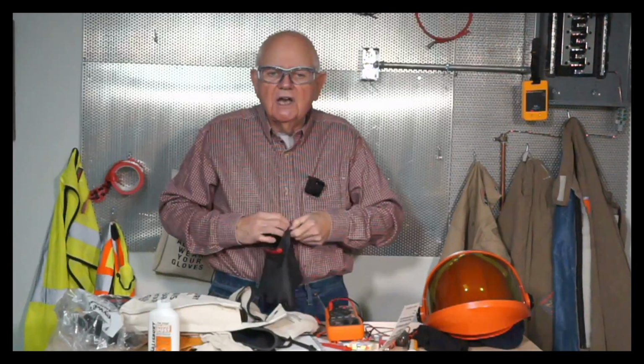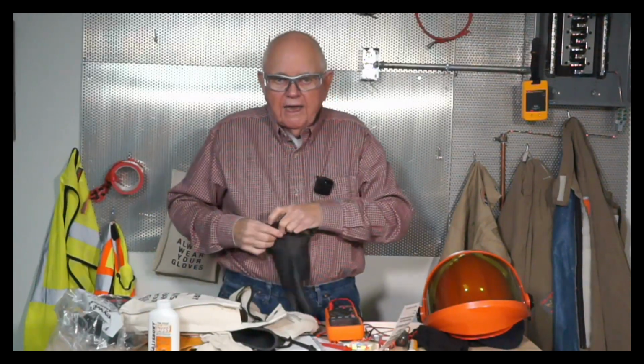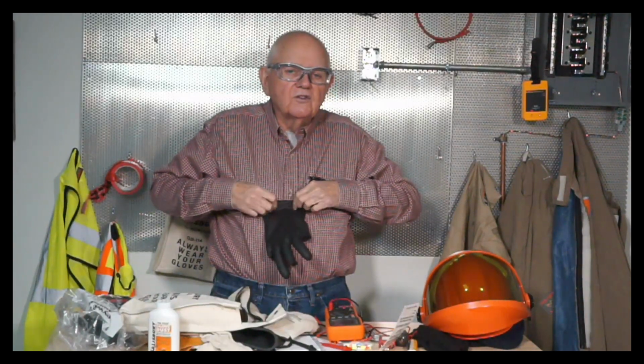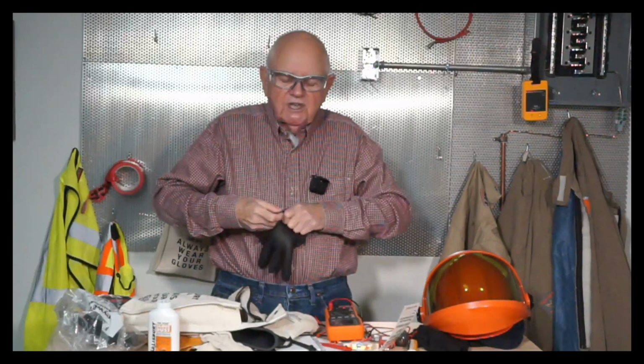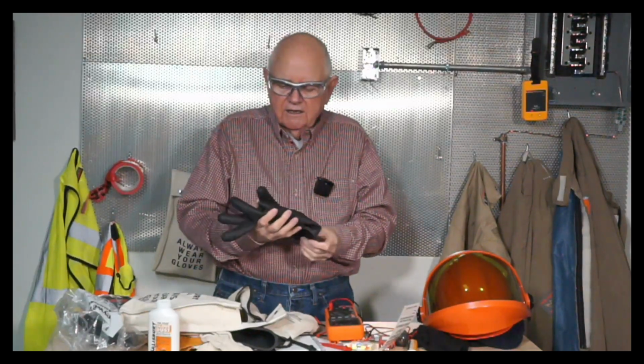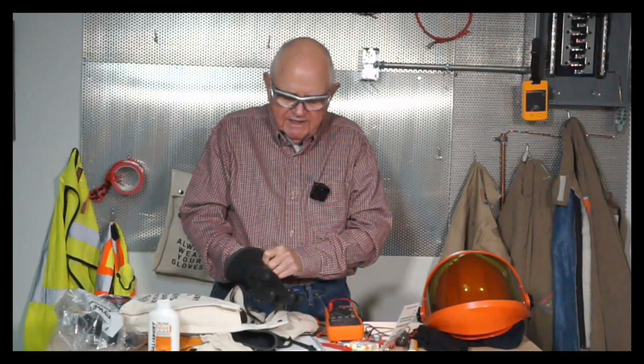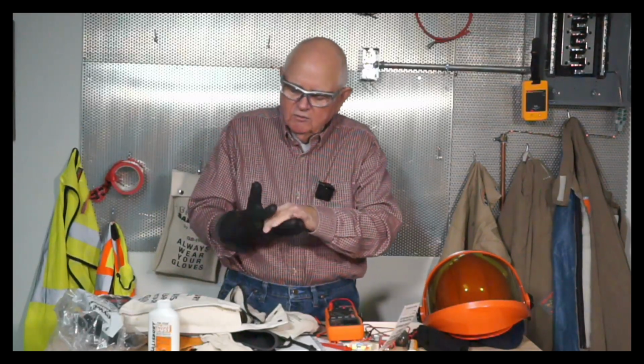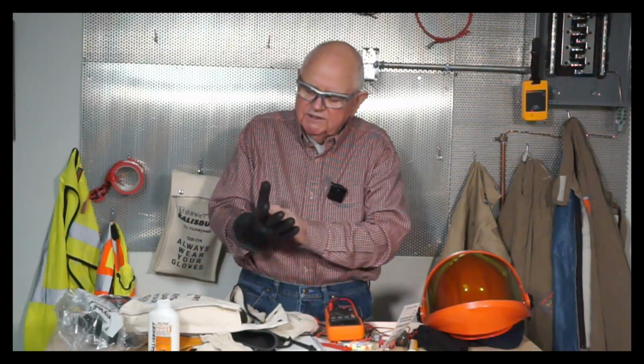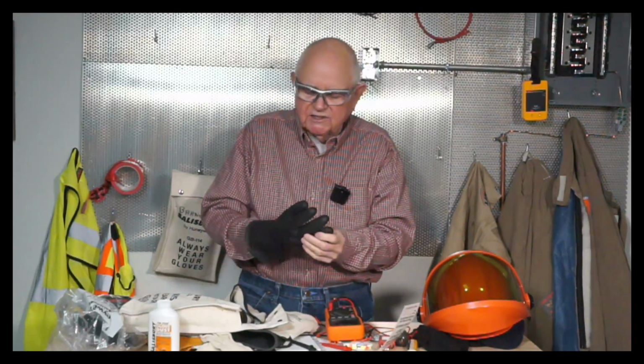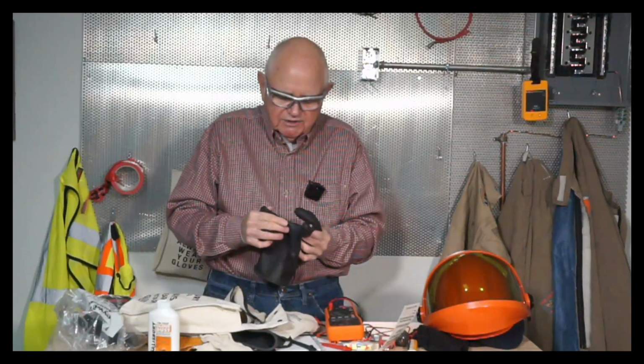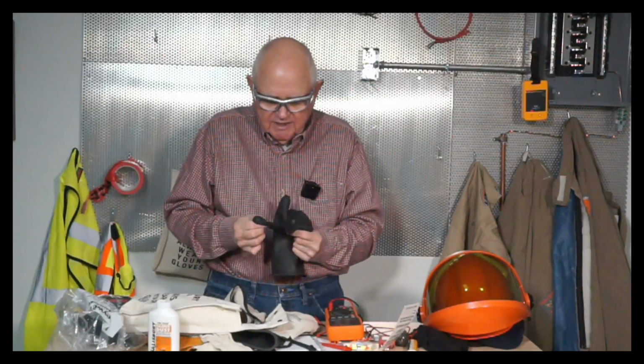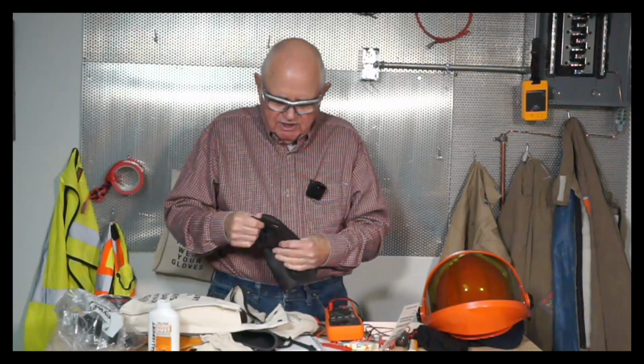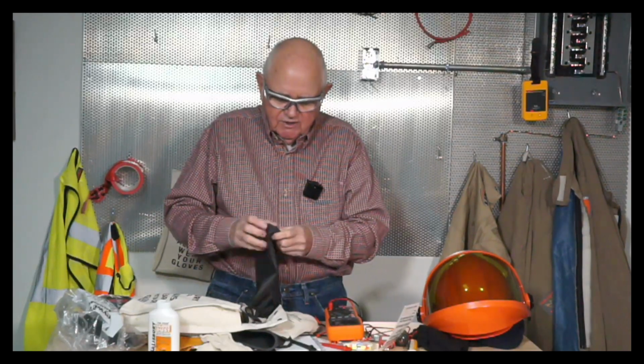Then on this particular glove, it's easy enough, I can turn it inside out. And I'm going to want to inspect the inside of the glove as well. I'm going to go through those same checks on the inside, and could put the glove on my opposite hand now. And once again, looking for any signs of deterioration, abnormalities. Any questions? Pull it out of service. Get it retested if you need to, whatever. Okay? So I check my rubber glove, make sure it's safe to use.